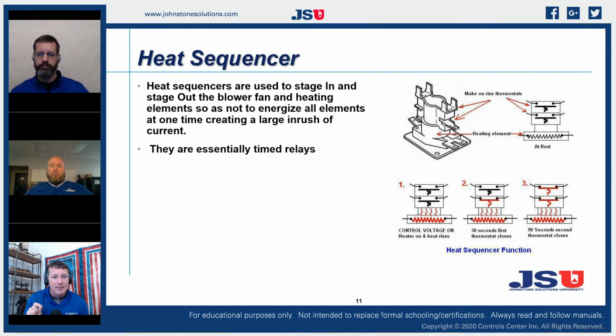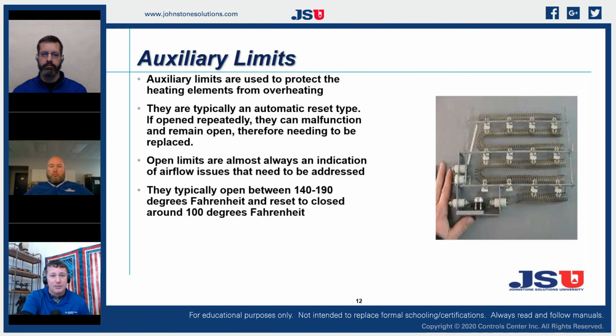So a heat sequencer is something that needs to be checked, and it needs to be replaced often. When you start seeing scorch marks coming out of the ends of our heat sequencer, when we start seeing dust building up around the contact points, it's time to replace those things, because that heat sequencer is the only thing that is going to time on that heater. If our timing starts wearing out, our heater is not going to come on. So I've had a lot of furnaces in the past that had heat sequencers that would stick, or that would not make, and therefore we don't have a functioning heat kit. So that was a common replacement part for me, and it should be a van stock. You should have a universal stack of sequencers on your van as a replacement component for electric furnaces.